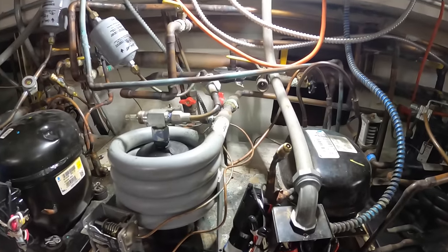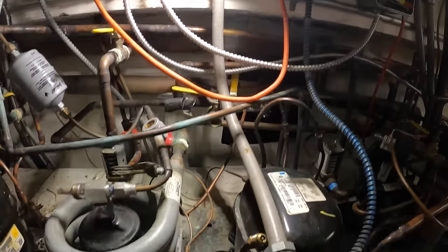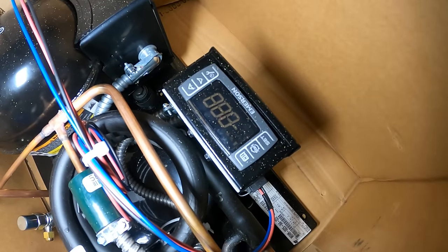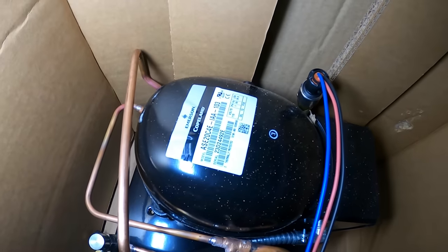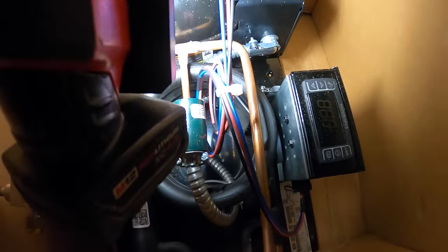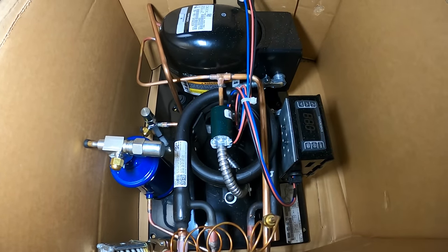It's time for an upgrade. As of right now we have two water connections — this is the water-cool condenser. This valve and this valve is closed so we shut off the water. Here's our new condensing unit — this thing is super nice. We have digital controls, a digital electronic unit controller by Emerson, a nice Copeland compressor, a liquid receiver, a water-cool condenser, a suction transducer, a high-side pressure control, and it comes with the water regulating valve. This is going to be a very nice upgrade.